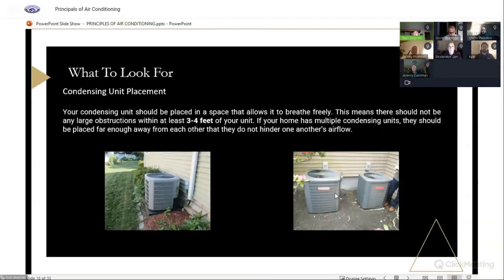Under a deck, I've seen many. The theory is it's cooler under there, the sun's not baking on the condensing unit, but do we have enough airflow? Is there 3 to 4 feet above the condensing unit where the deck platform is? So you can call those out.